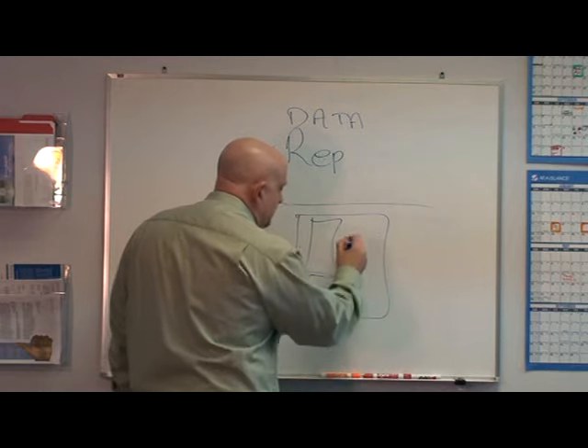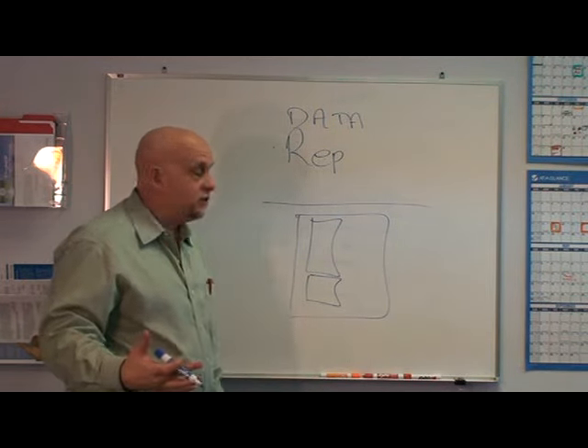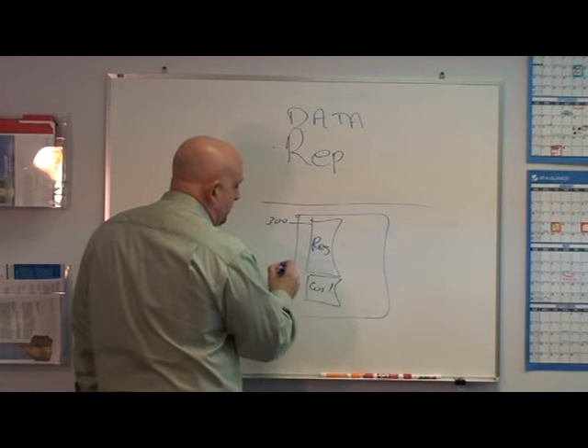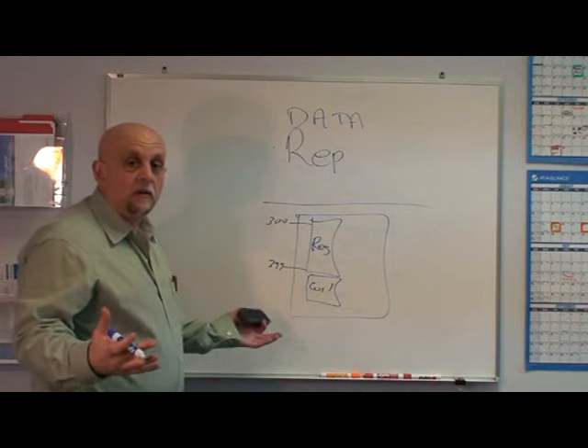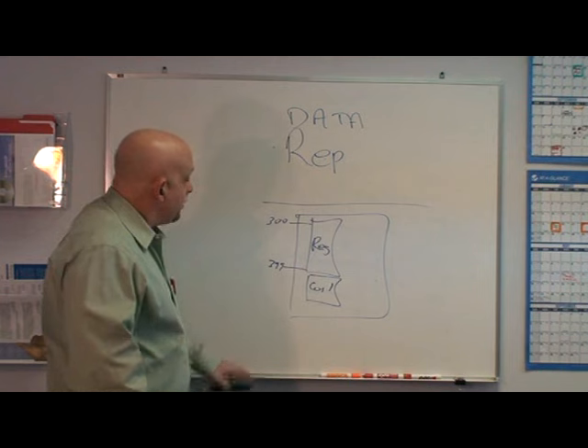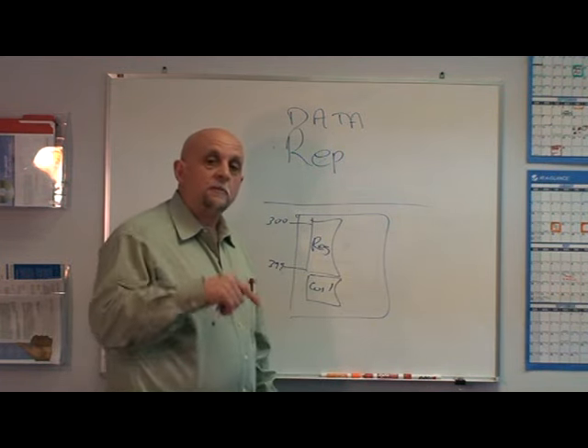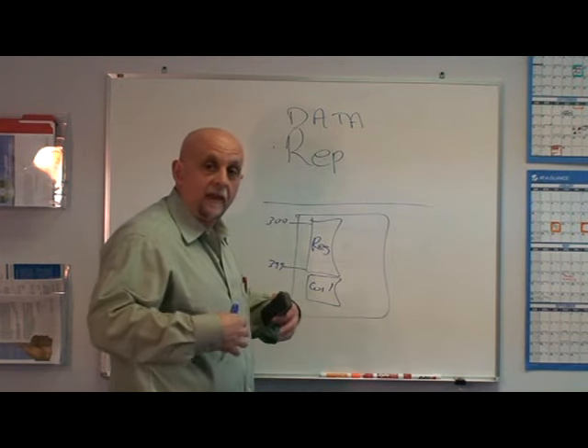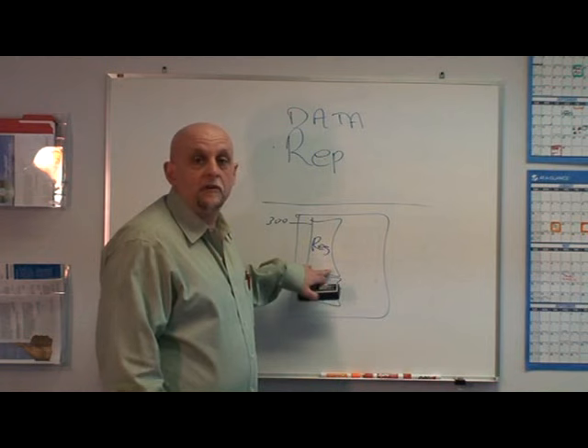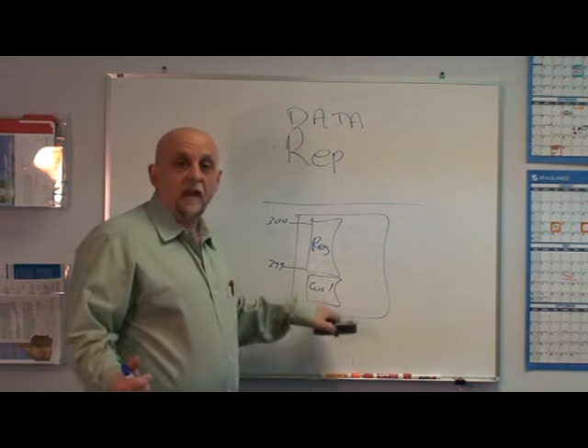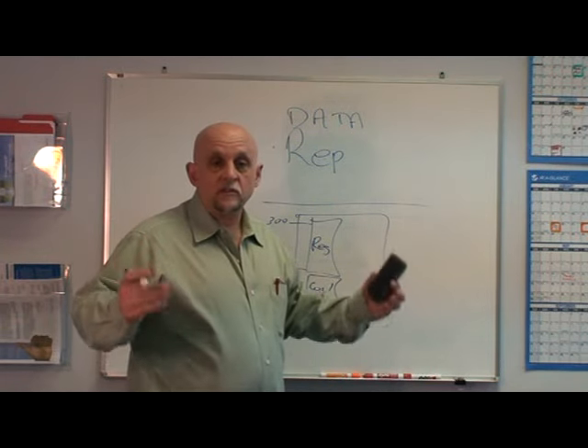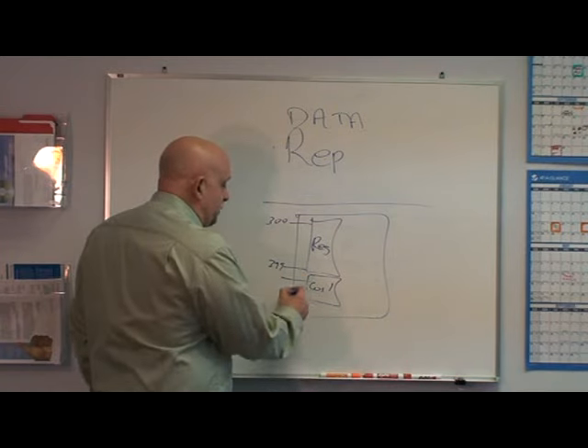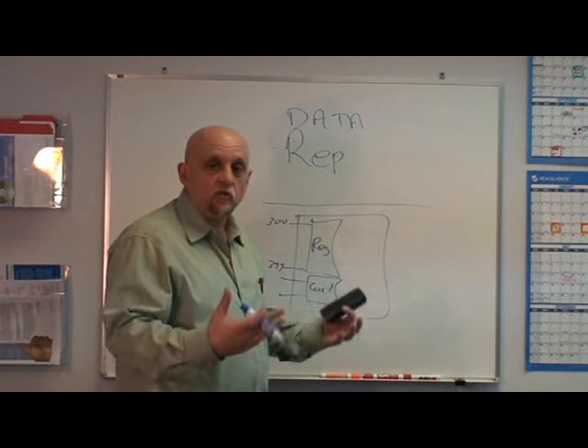The other thing that they pick is the data space, which leads us to the next very important point on Modbus: how is data organized? They allocate some sort of memory inside a device when you're designing a Modbus RTU device, that this is going to be my register area, this is going to be my coil area, and I'm going to start this at, say, 300. I'm going to have 100 registers, so this is going to be 399. So it's up to the designer to say I'm going to have this register space with 100 unsigned registers. Now, there's two kinds of registers. There's actually input registers, which come back from the old days when this was for PLCs, and you had IO coming into a PLC, so these were actually like analog inputs. And you have holding registers, which are nothing more than internal registers. Same thing with coils. We've got status coils, which just say what's the current state of this coil, or you've got input coils. Input coils are almost like field inputs, can be field inputs, but people are free nowadays because we're not tied to IO all the time to use these in any way they want.